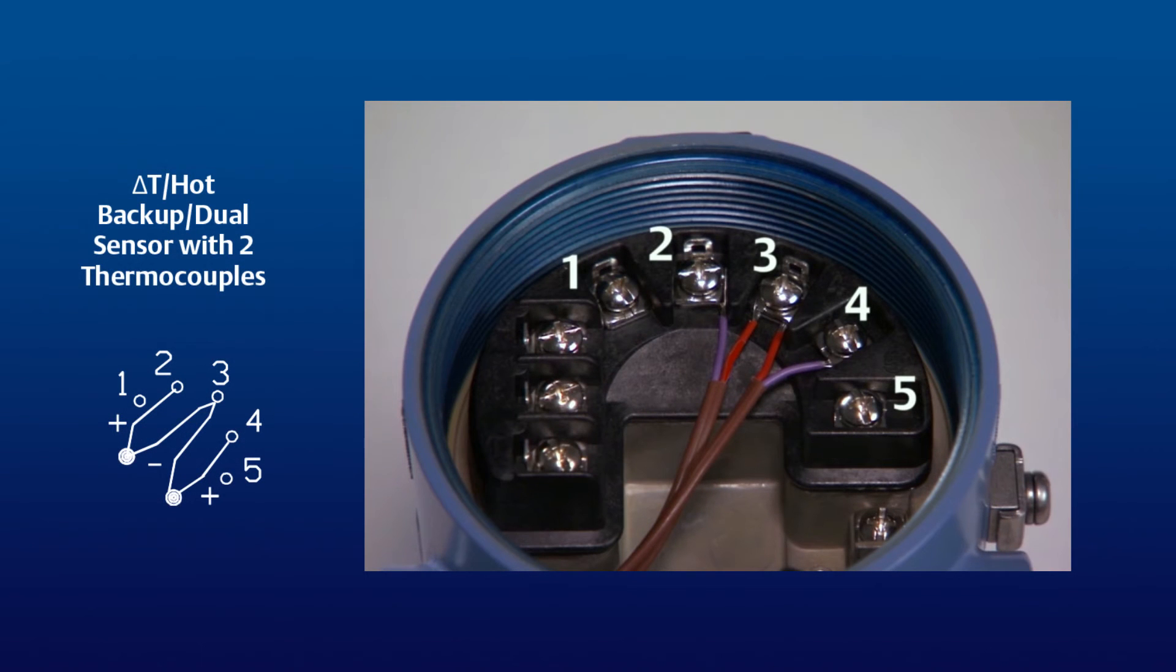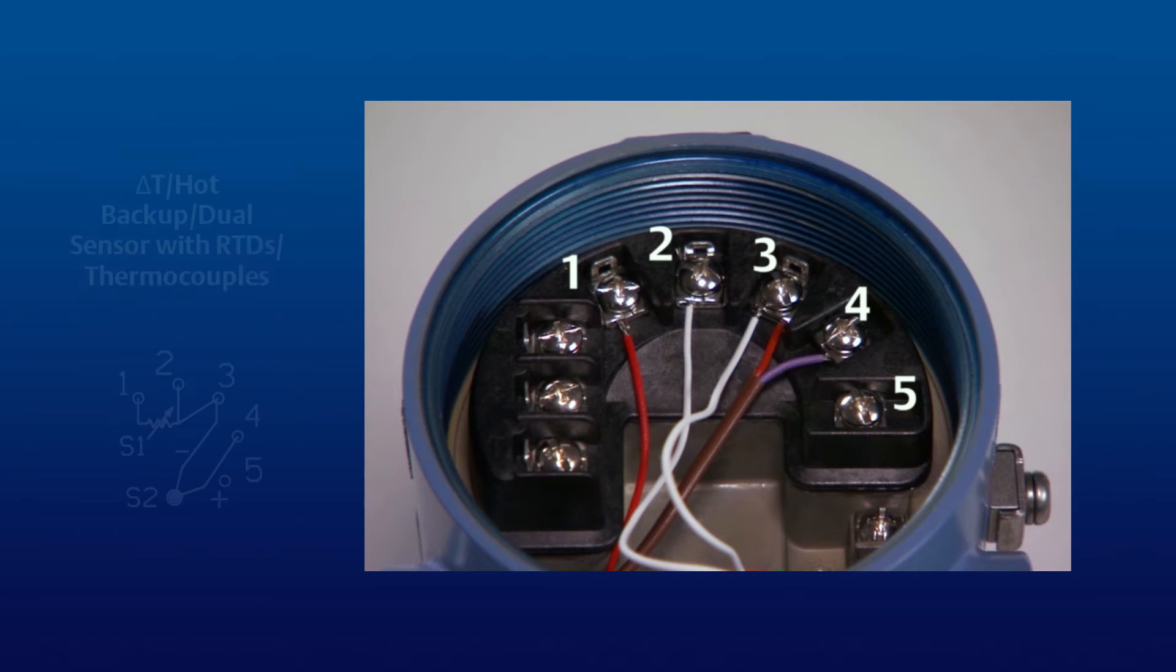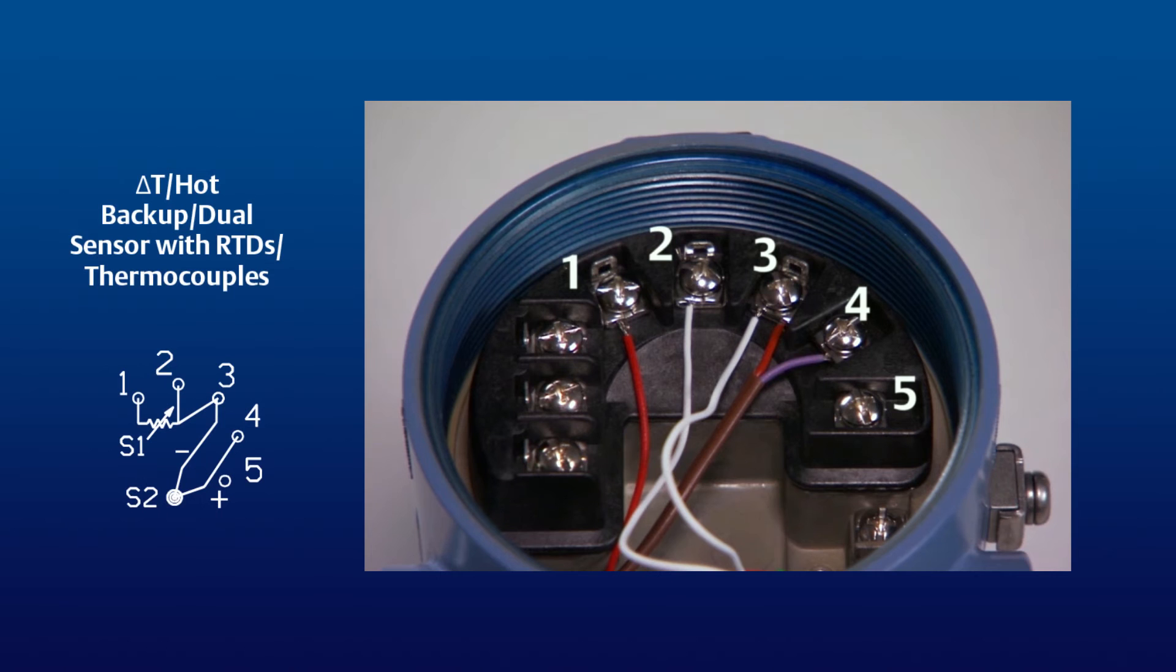Here is the proper wiring configuration when using two thermocouples. Note that for the first thermocouple, the positive wire is connected to terminal 2, and the negative wire is attached to terminal 3, along with the negative wire from the second thermocouple, while the positive wire is connected to terminal 4.